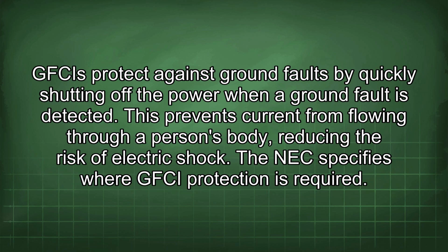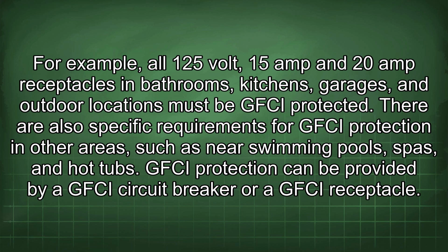GFCIs protect against ground faults by quickly shutting off the power when a ground fault is detected. This prevents current from flowing through a person's body, reducing the risk of electric shock. The NEC specifies where GFCI protection is required. For example, all 125-volt, 15-amp and 20-amp receptacles in bathrooms, kitchens, garages, and outdoor locations must be GFCI protected. There are also specific requirements for GFCI protection in other areas, such as near swimming pools, spas, and hot tubs.